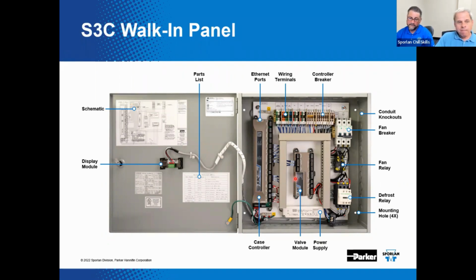The display module, which of course we can only see the backside of - because you'd want to be able to close the cover and then see what it's telling you, right? Wouldn't that be useful? So it would also have the fan breaker and relay, defrost relay, and any other components needed in there. And you could use it to control discharge air temperature, lights, defrost, fans, and the circuit EPR.